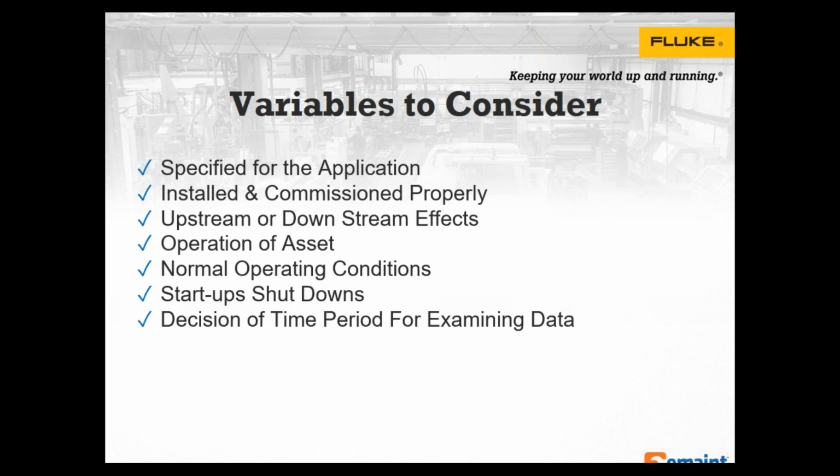Keep in mind some assets aren't as complex as others. They come in many different varieties and forms. I like to say, is this part of a system, or is this more or less an autonomous type of asset? Again, temperature and pressure transmitters and some devices are pretty straightforward, and you could set limits. But for more complex assets, there needs to be enough data to be confident that, yeah, I'm truly at a baseline condition here.